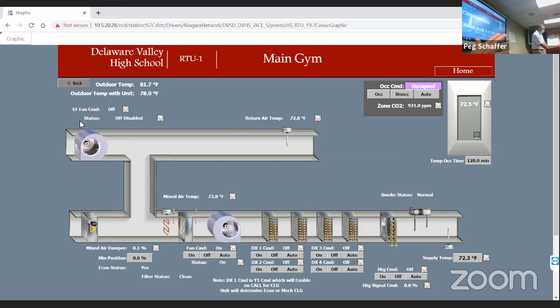But it's a wonderful tool to utilize, again, to increase efficiency by not having to physically go and look at parts and pieces. You can view this information from any computer that's on the school's network. Yeah, adding to that, each teacher has their own level of temperature, so we can tailor and customize each room to that teacher. Some like it a little warmer, some like it a little cooler. If you're on a system that covers several rooms, it's hard to do that. But with this automated system, we can pretty well set the temperature within a degree. Yesterday I had a teacher write a work order saying it was warm. We checked the airflow coming in, and the temperature in the room was 70.1. Now, 70.1 is probably pretty good for the rest of us, but we dropped the temperature a degree. She's happy.